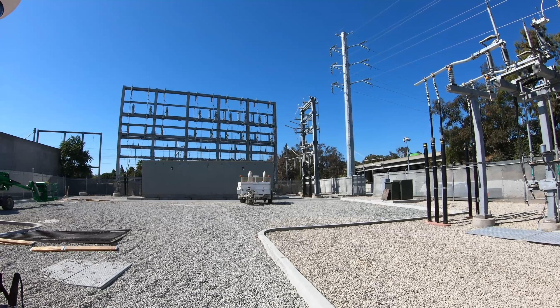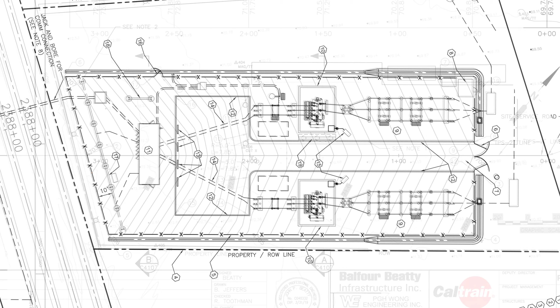Moving on, you can see now this is the 25 kV disconnect switches coming from the step-down transformer. These switches or breakers will be automatically controlled either from the control building or in the future remotely from the JPB Power Control Center. The 25 kV circuit is then taken underground, goes up the gantry, and into the control building. Now, the purpose of the control building is to provide the access to manually control the entire substation locally, or the interface with the Power Control Center at JPB.